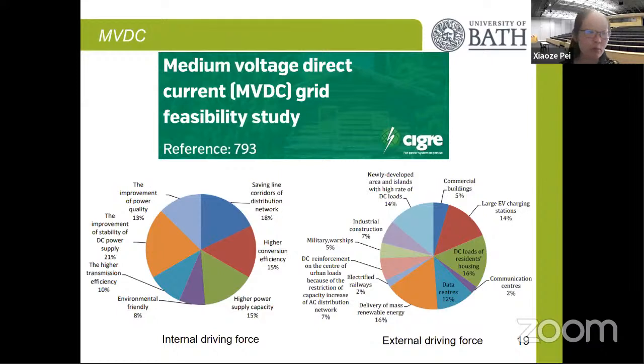Now I'm going to move into the medium voltage DC grid and go through the DC fault current limitation and interruption in this area. Why do we pay attention to this? Because there is a very growing need for medium voltage direct current. So this is a feasibility study led by CIGRE, and it's looking into the internal driving force.